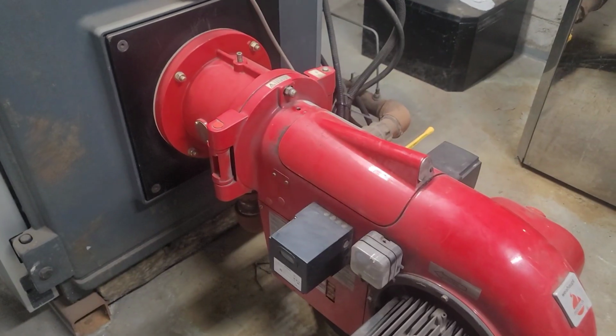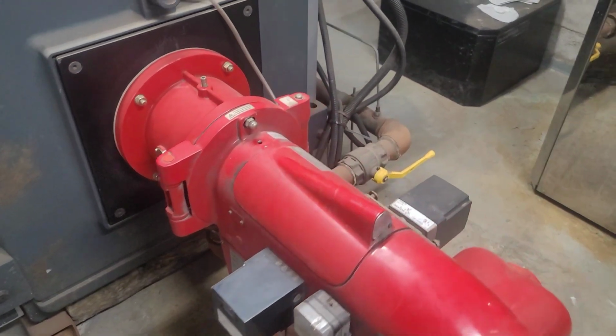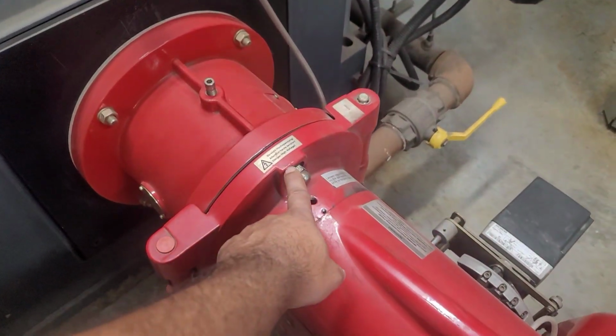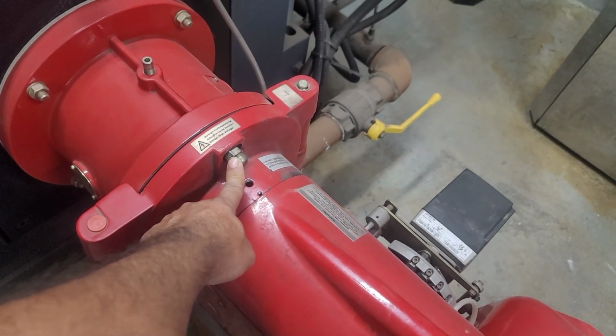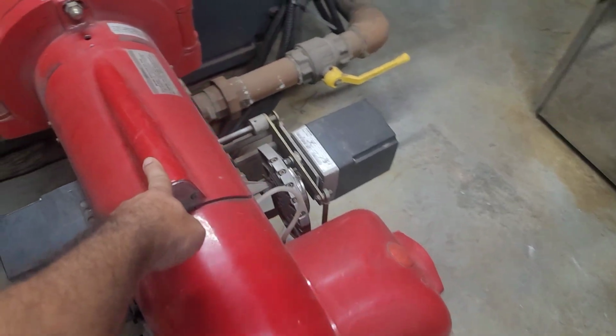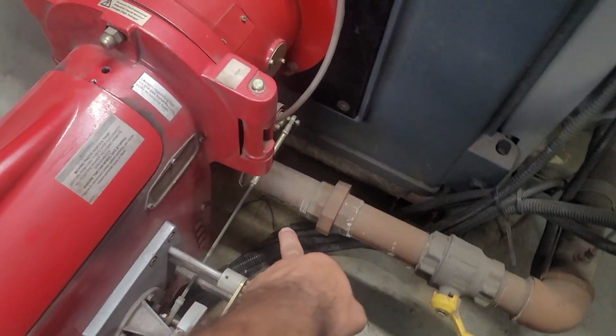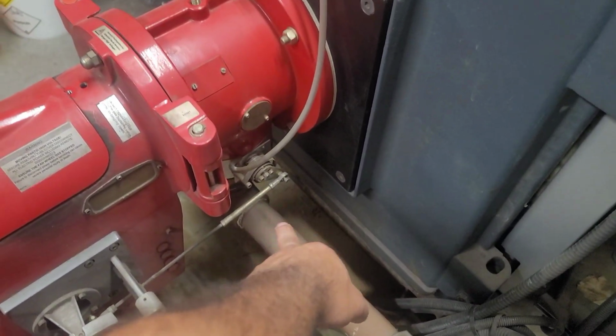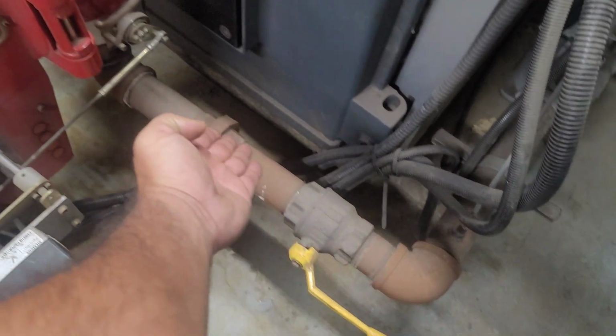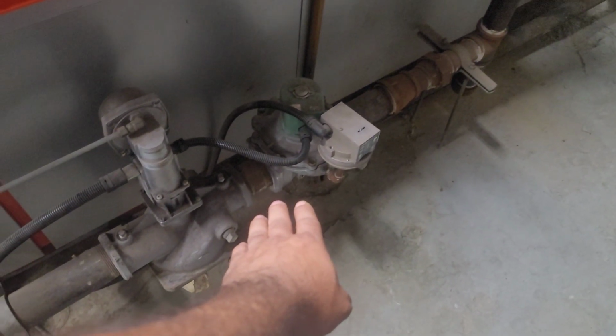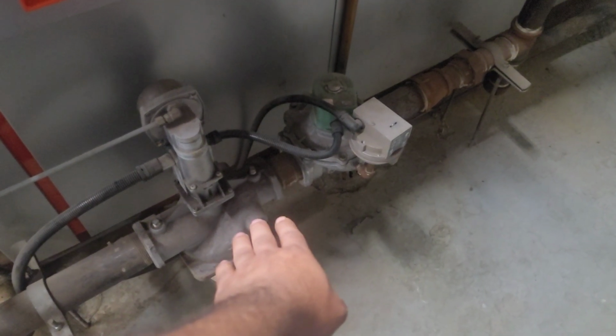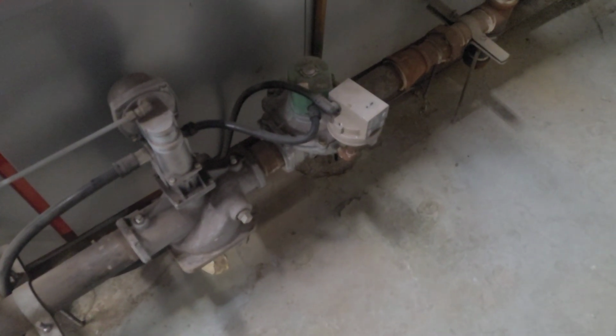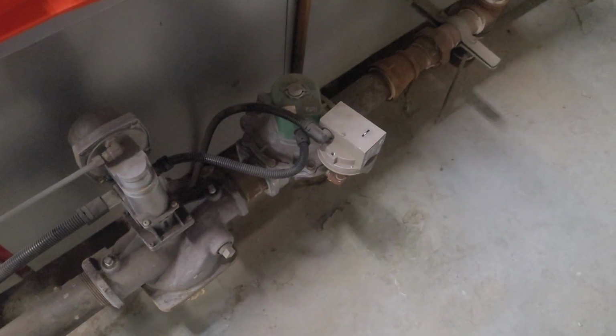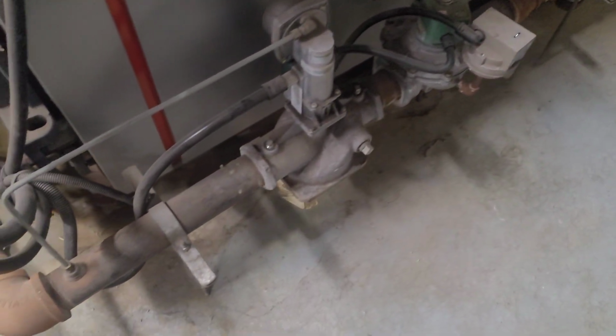So the opening of this burner is very easy. We have to take this nut out, this plate out, and this link which modulates the gas, which is coming from the gas line, from the gas train. And these are the high pressure and low pressure switches, which are also combined with the regulator, which also reduces the pressure.